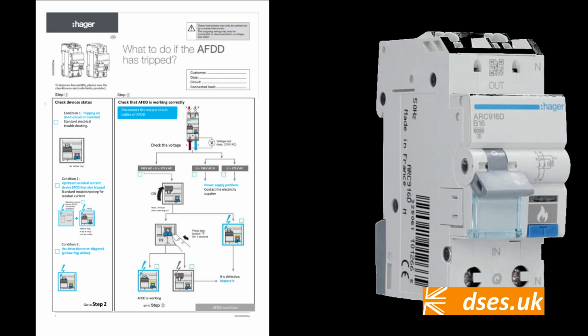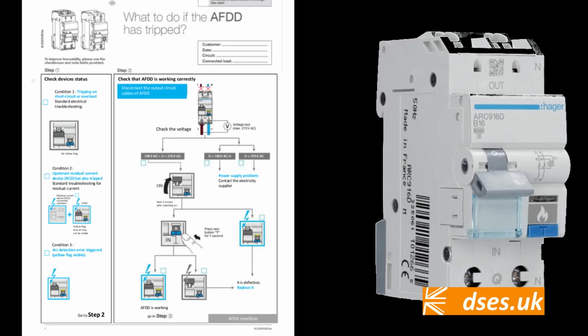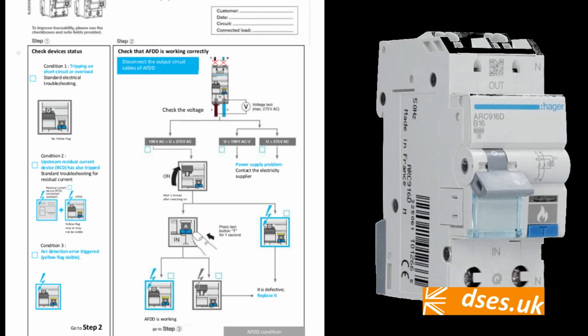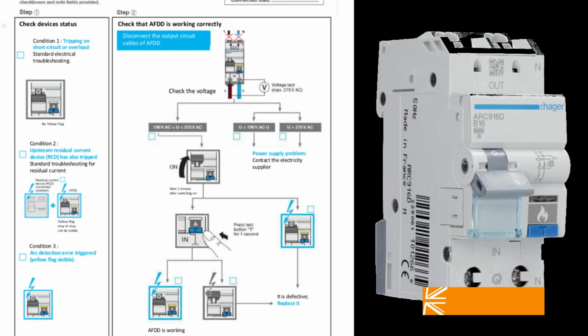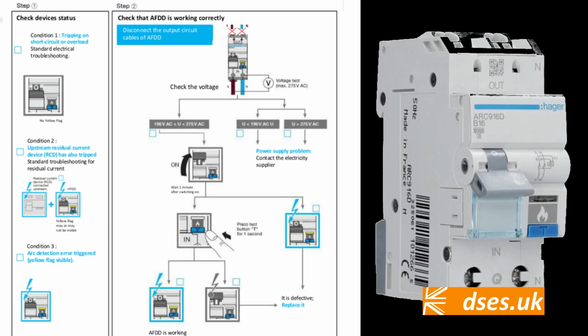Well, apparently they don't make a combined RCD AFD device at present, so their AFD units are combined with overload protection and shun the use of an illuminated indicator completely. Instead, they have a mechanical yellow flag which will be absent for an overload fault, present on an arc detection, and may or may not show in the event of an external RCD trip. The fire symbol below the flag window supposedly means arc rather than overcurrent, although I would have thought a lightning symbol would have been better. It's not like an arc can cause a fire but an overcurrent can't.